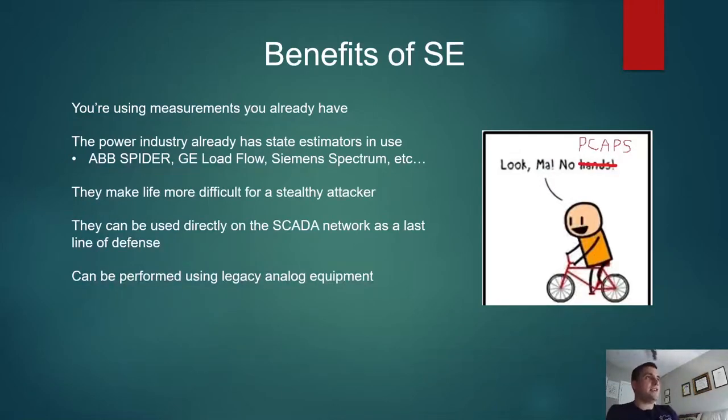Benefits of state estimation are, one, you're using measurements that you already have. That's probably the biggest one. So as far as defense in depth goes, this doesn't require doing any tricks to add normal commercial off-the-shelf IT security technology onto an OT system, which is a big plus. And if you work in the power system industry, you already have these. ABB Spider, GE Load Flow, Siemens Spectrum, there's lots of commercially available state estimators out there for the power industry that were not designed for security, but could be potentially utilized for security. It makes life much more difficult for an attacker to be stealthy. If an attacker's attacking your sensors, especially if you have lots of accurate redundant measurements, they need to be much more careful about how they manipulate those measurements to avoid detection.